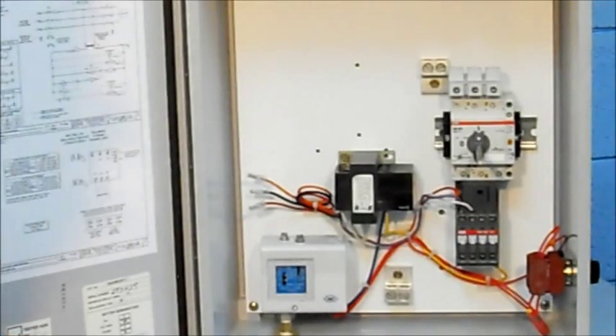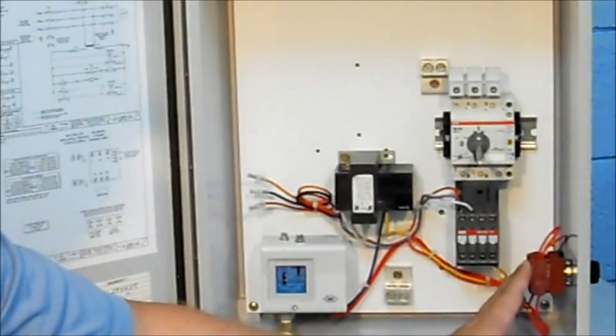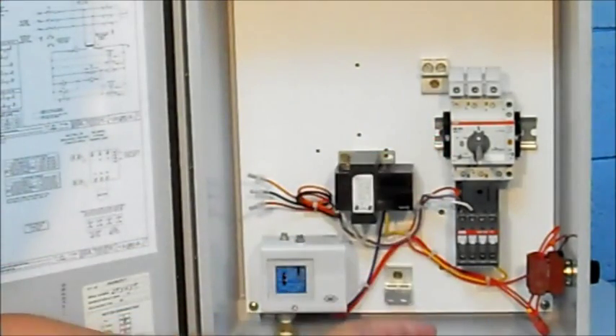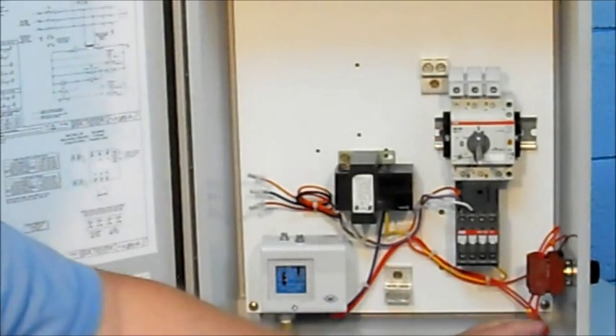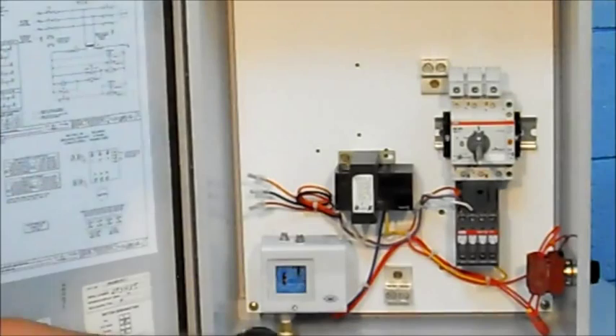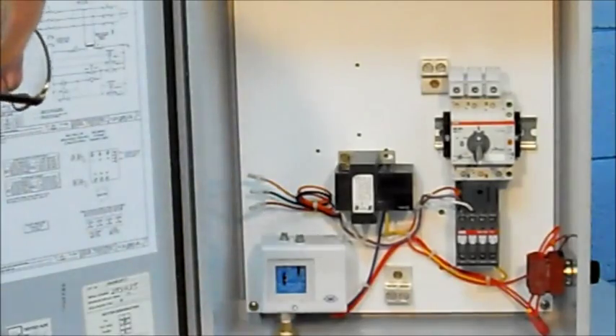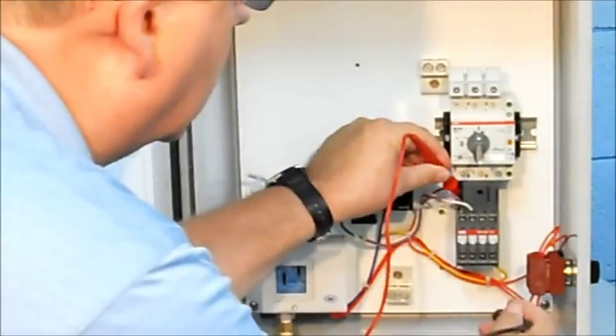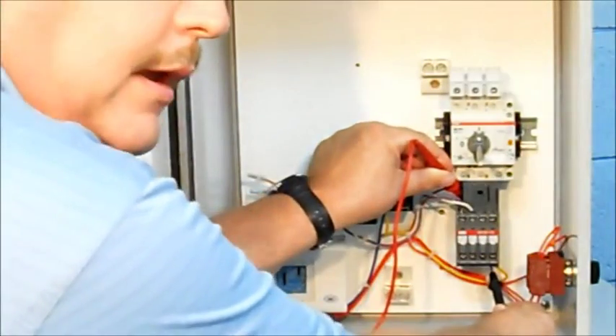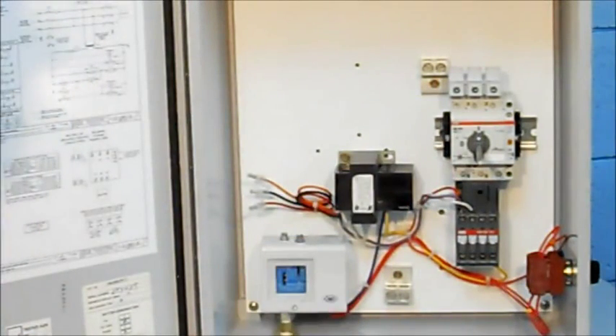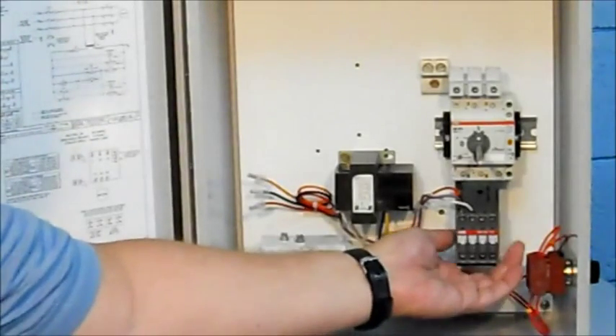Okay, now for a little troubleshooting. If the jockey controller does not run when placed in the hand position, of course you want to make sure that your isolating switch is closed, but you want to determine if the problem is in control wiring or the coil of the contactor. By taking a voltmeter, you can measure the voltage on the coil connection as shown here. For the contactor, if that coil voltage reads 24 volts AC, then you have the proper voltage to the coil, it's just not energizing to pull in, and you probably need to replace the contactor.